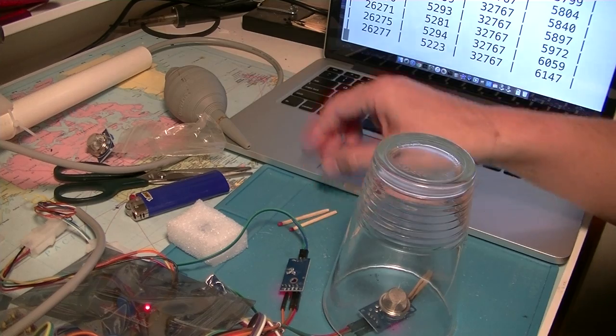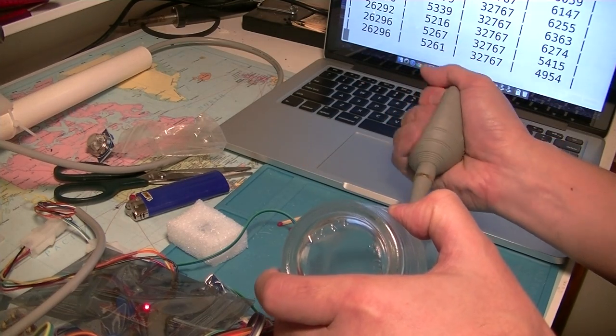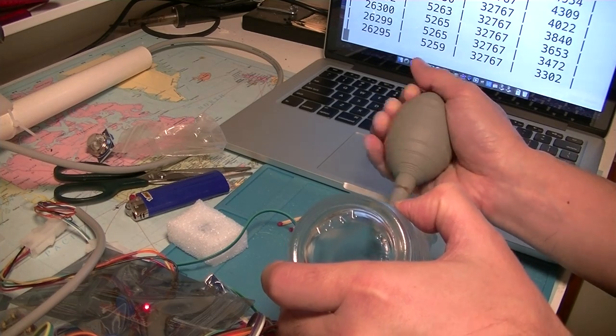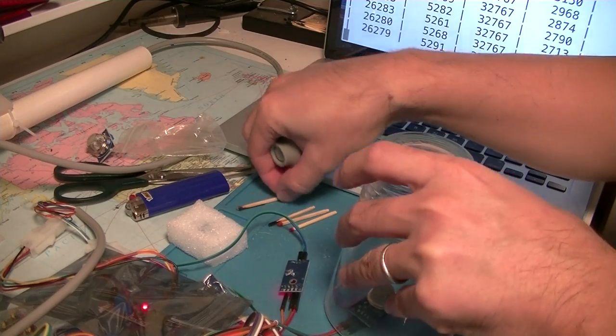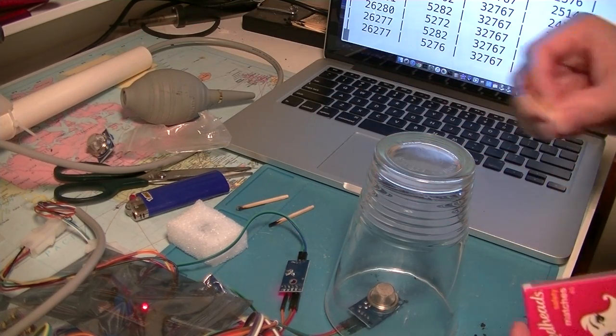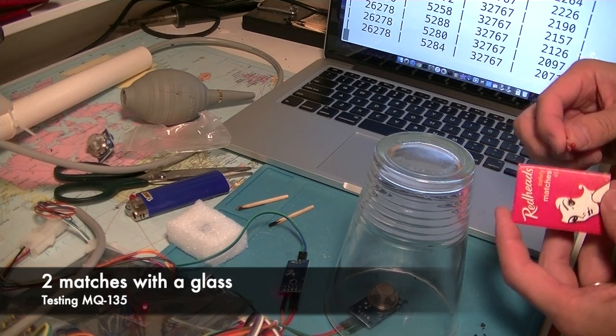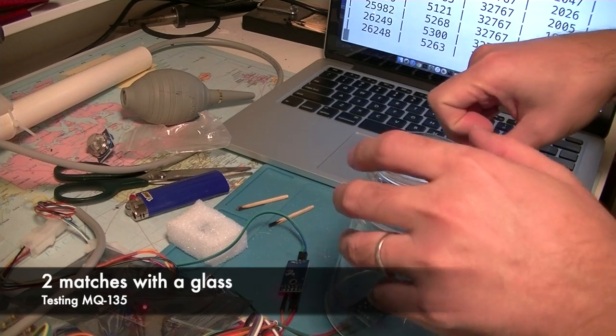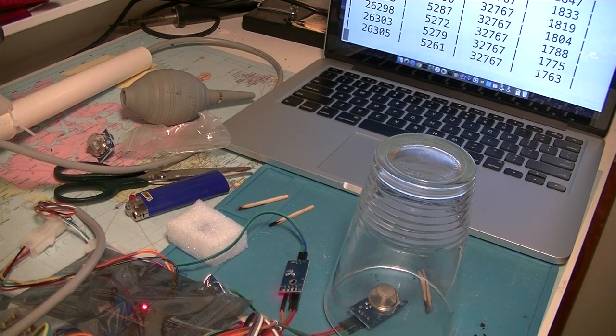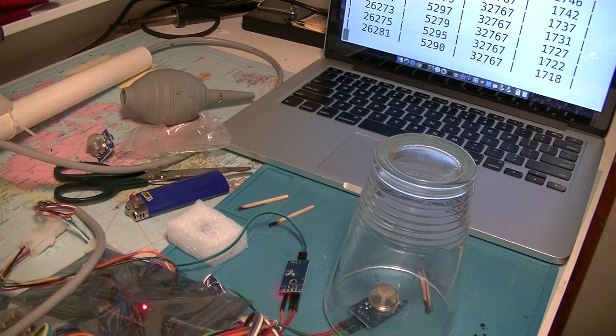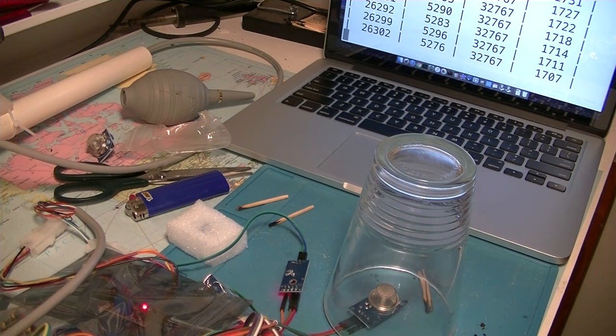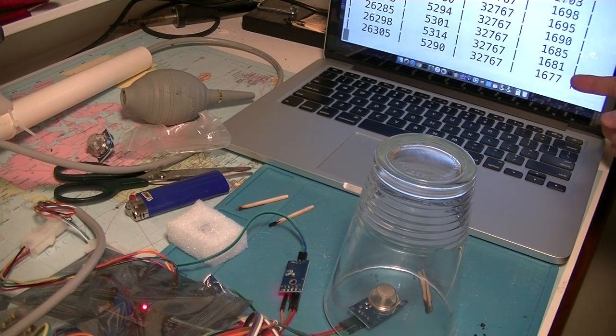I'll clear the lighter gas. Going back to 2000 level. And I'll try one, two, three. Quite a lot of smoke going into this glass. No, it does not change much at all. It's still sitting on 1600.